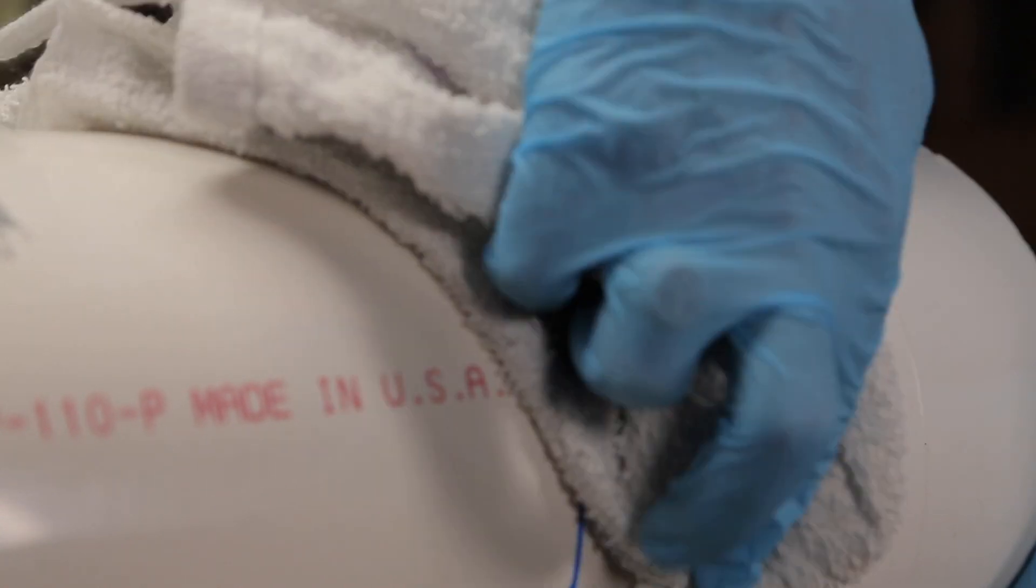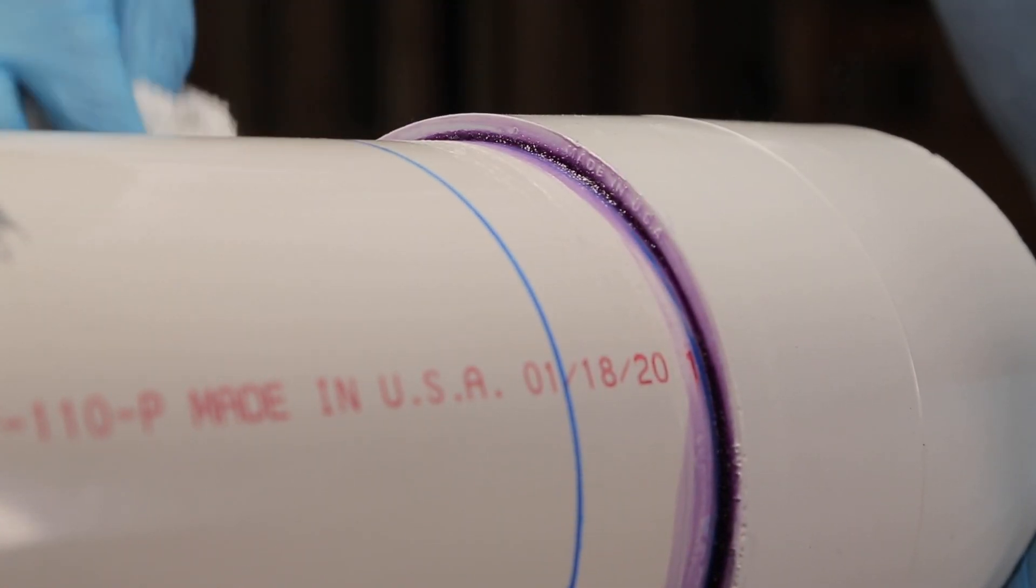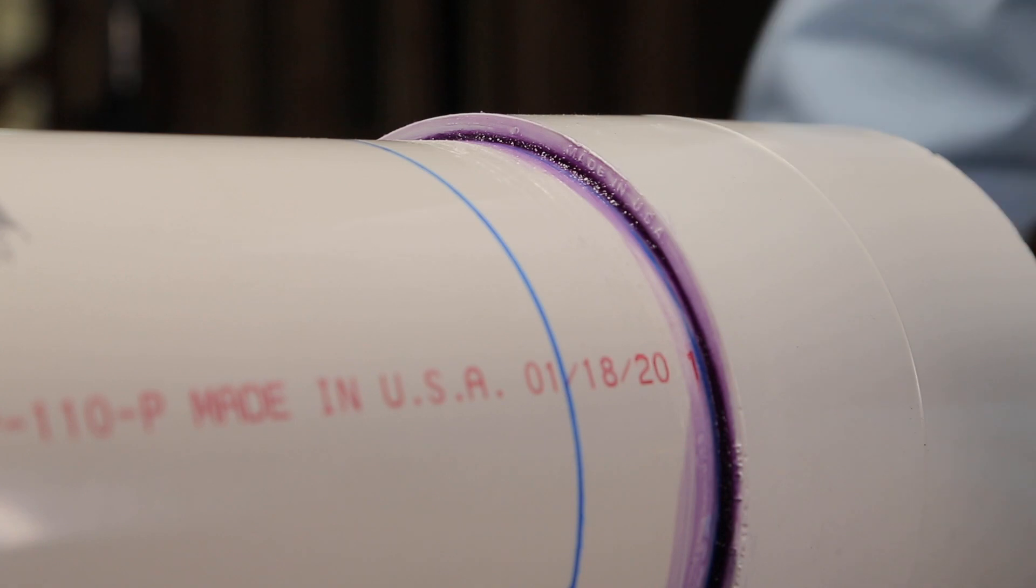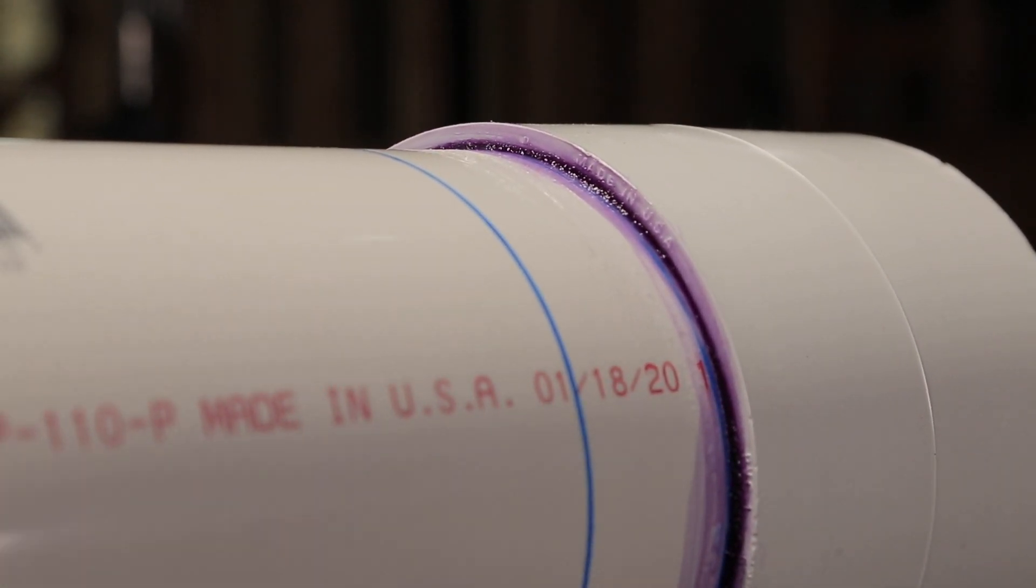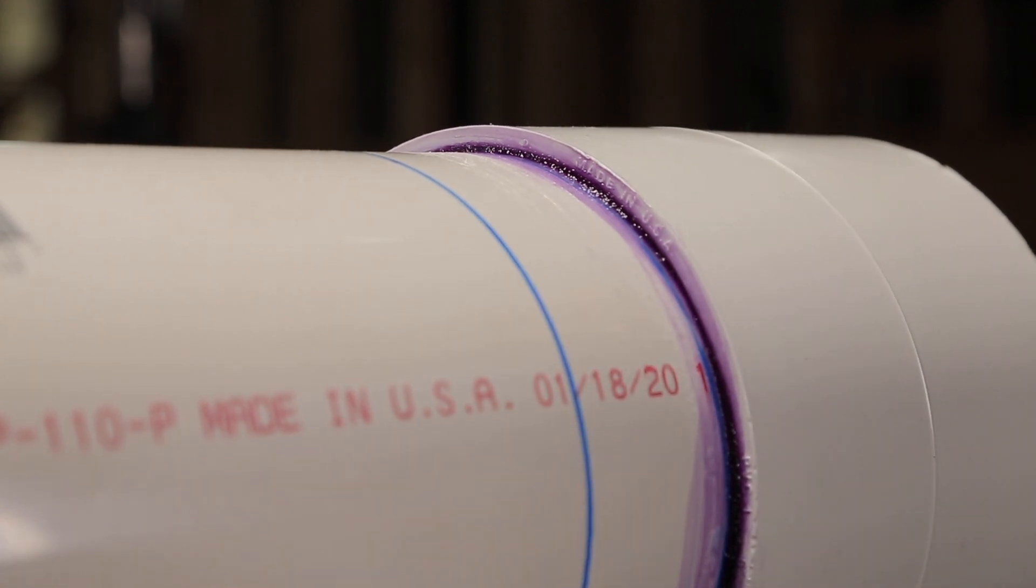Lastly, remove excess cement from the joint. A properly made joint will show a continuous bead of cement around the perimeter. If you see gaps, you might not have applied enough cement and the joint may fail.